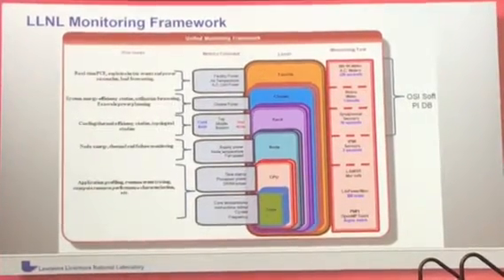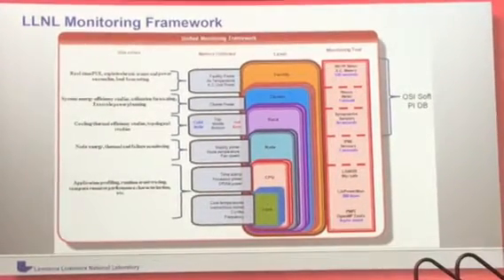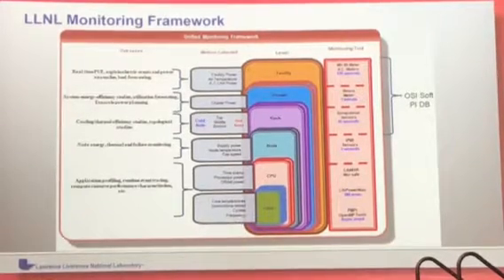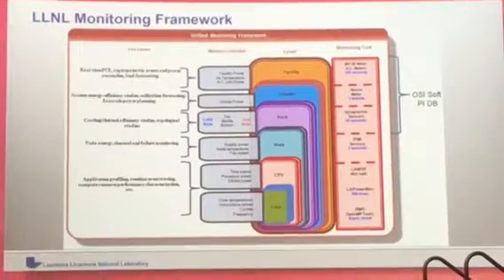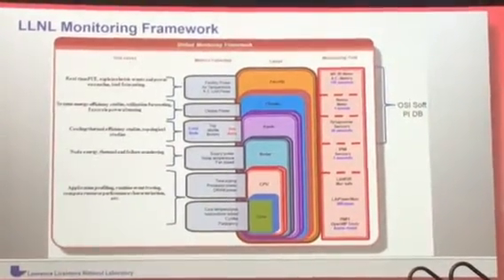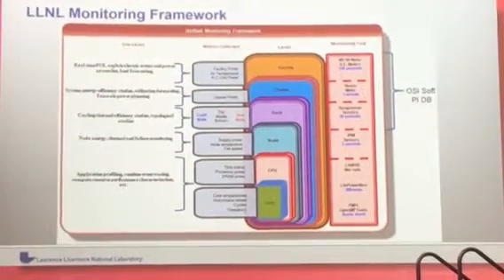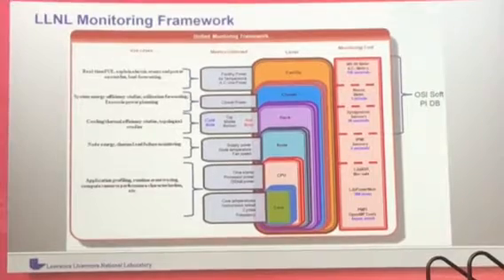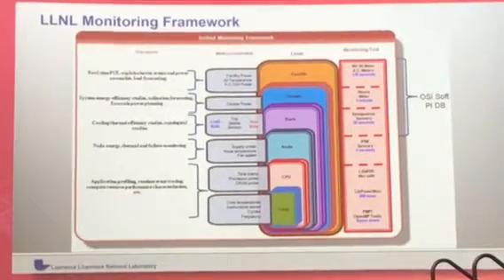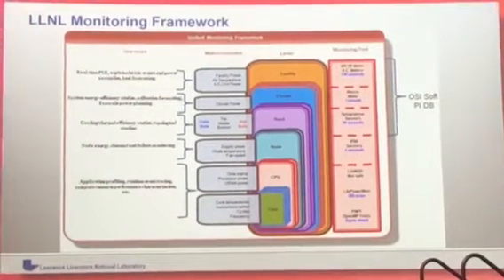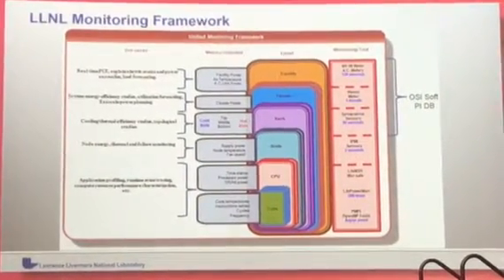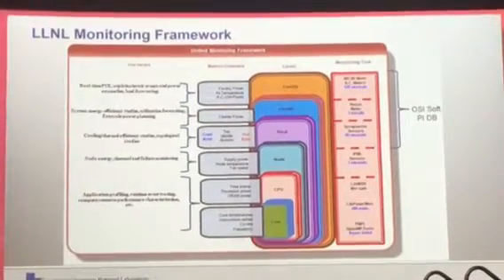So this shows basically our framework of how we meter our systems, our power, our mechanical systems. On the facility side, it's kind of hard to read, but we use our software to watch the electrical usage down to the cluster, rack and node side. The system administrators look at the actual node temperatures, the thermal data that they can take in, and down at the CPU and core level, the actual users. So there's a lot of synergy that needs to be involved, but mainly on the node, rack, cluster and facility side, we're very interactive with our system administrators to look at the data, and it all goes back into this OSIsoft database so that we can look at our trends and analyze any electrical issues, and analyze it through our BMS system.